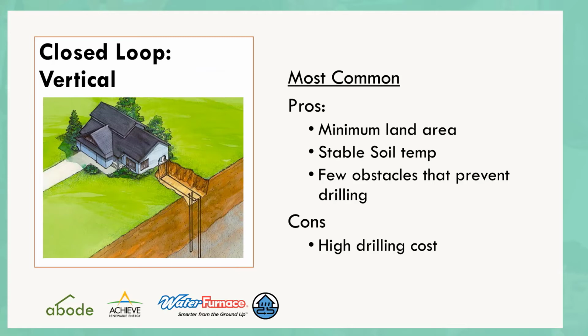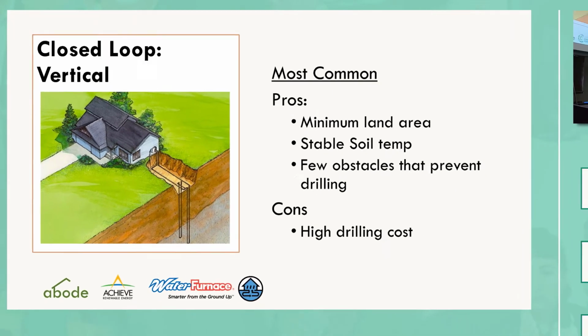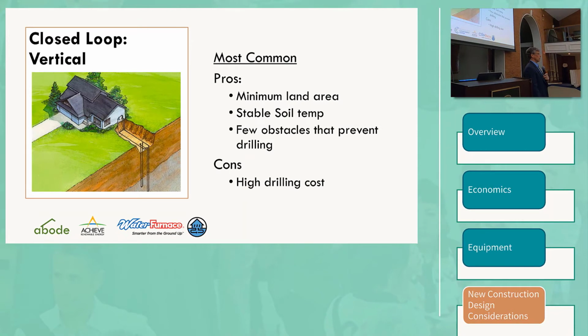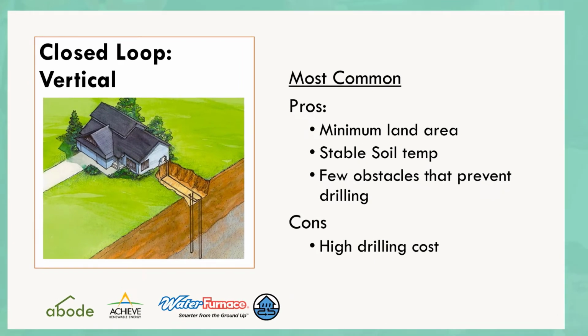So the most common installation is a vertical closed loop. For a typical house, that would be 1 or 2 borings, so it takes about the space of a parking spot, and everything's finished below grade. And so you can have driveway over that, you can have building over that if you want, landscaping, whatever you want to do. Just don't put it someplace where you're going to want to dig for a pool or have to put a replacement septic system or something like that. And so it's very predictable in cost, but drilling is expensive in our area because that great thermal conductivity that we have in our rock also is because the rock's really hard and dense. So you need a bigger drill rig than you would use in other parts of the country.